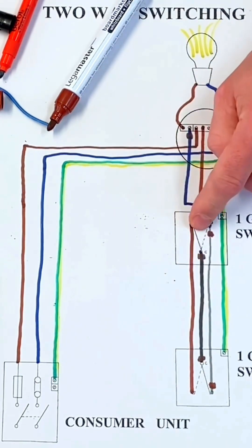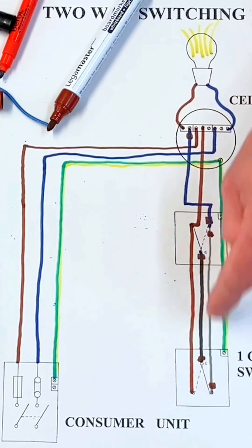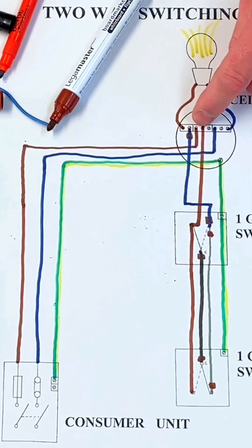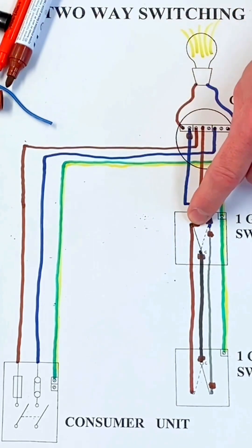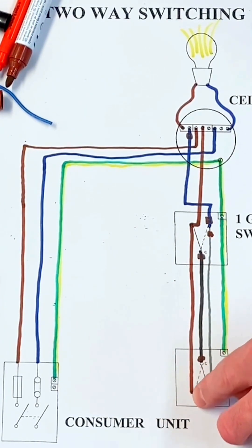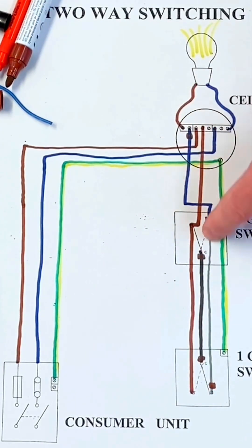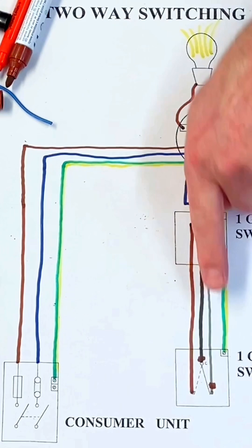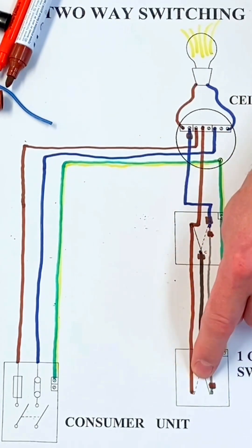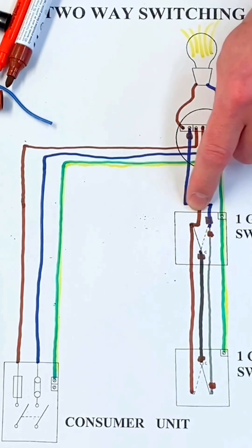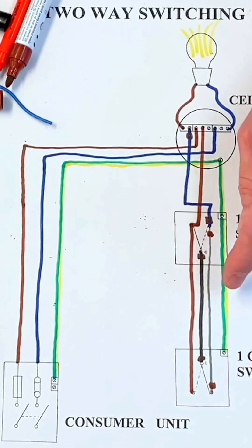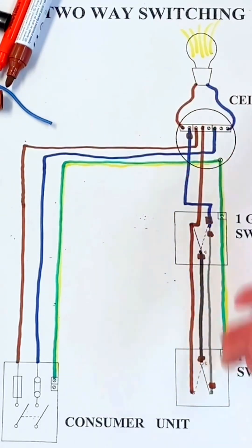How do I turn it off? If it's on, it doesn't matter which switch you turn - whichever switch you operate, it should go off. So let's move this one fictitiously into the other position. This blade is now over here, so the permanent line comes in through the loop down here, but this blade is now open - so it doesn't turn it on. In this position the light is on. If we turn both blades, we can follow the line through down here - this blade would be over, it would come back at the common, and the lamp would illuminate. So if it's off and you operate one switch, the light will come on. If it's on and you operate one switch, the lamp will go off.